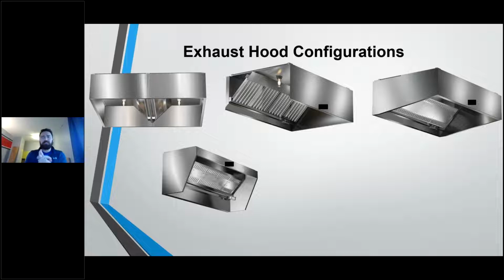And then you're going to have a reduction in CFM in utilizing these hoods. Thing to keep in mind is, as soon as you have ovens, or really hot appliances underneath these hoods, like you couldn't, for example, in most instances, have a gas-fired charbroiler under a low proximity hood, because the heat of that charbroiler would be sitting too close to the fusible links in the fire suppression system and would cause the fire suppression system to go off.